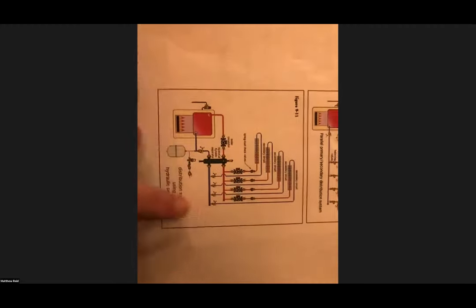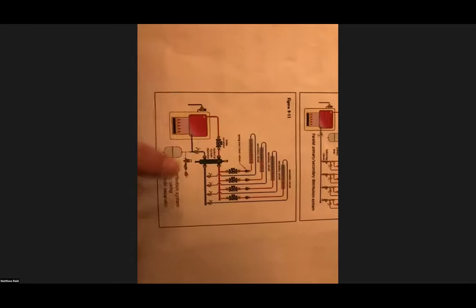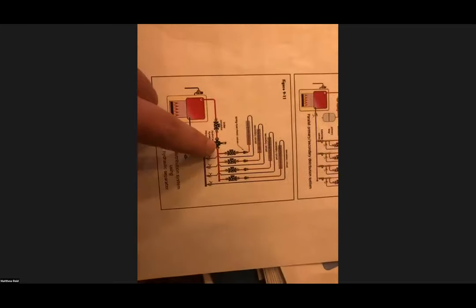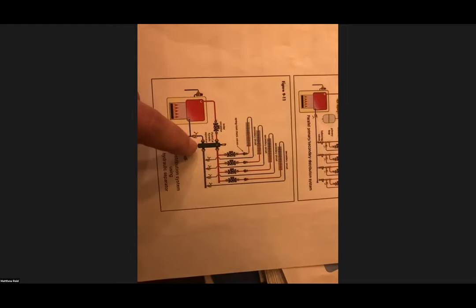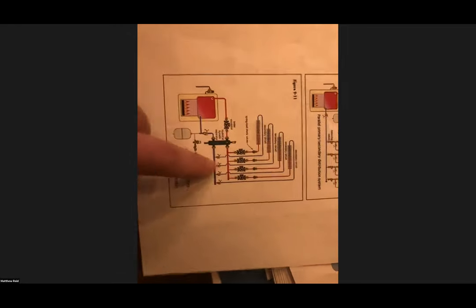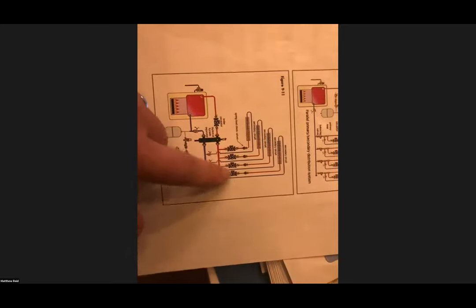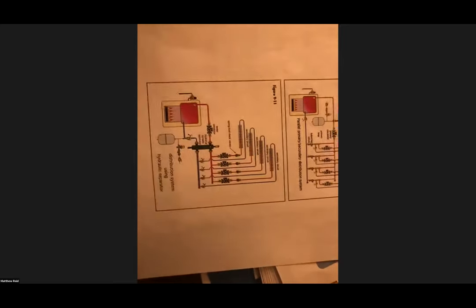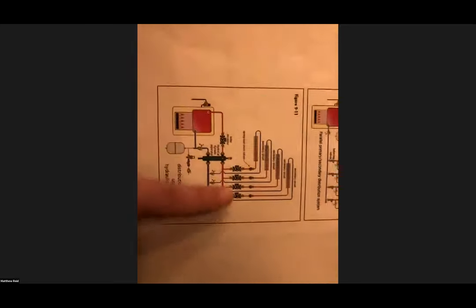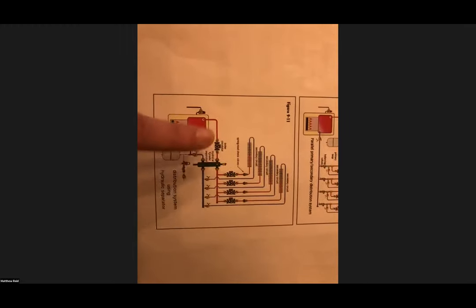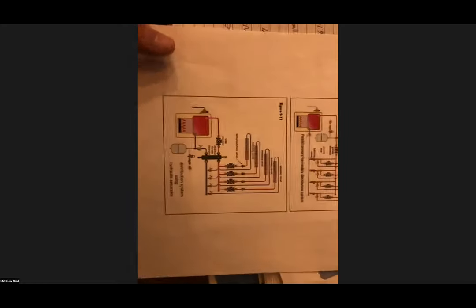You do whichever one you so desire, but this is a very good representation of what a common hydronic system looks like nowadays. Boiler, hydro sep, it's got our air, dirt, and magnetic built into it, back into the boiler. The system does its own thing with each pump on its own header, doing its own thing that it needs to do. This flow on the system side never interferes with the flow on the boiler side. And that's extremely common. This is actually the vast majority of ways that I design my systems nowadays.